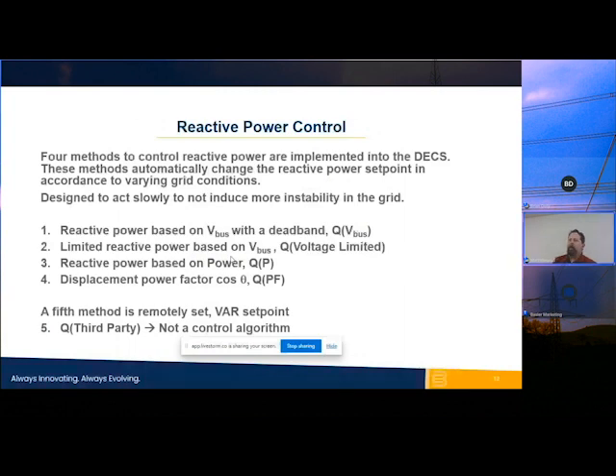So let's talk about the reactive power control. The reactive power control is really where the voltage regulator does the majority of its work in its lifetime. Once we're parallel to the grid, voltage is hopefully very stable. At that point, the voltage regulator, by increasing or decreasing its amount of excitation, is pushing or absorbing reactive power, or VARs, into or out of the grid.